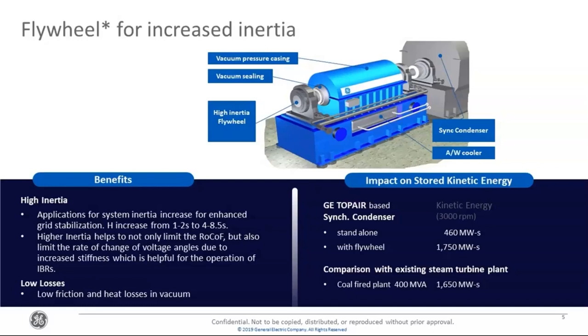which on its own had an inertia constant of roughly 1.5, a kinetic energy of 460 megawatt seconds. But enhanced with the flywheel, we were able to get a kinetic energy of 1750 megawatt seconds, which roughly translates to an inertia constant of about 6 for that machine. And that is very much comparable to a traditional power plant, like a coal-fired power plant of 400 MVA, which gives roughly the same amount of kinetic energy, right?